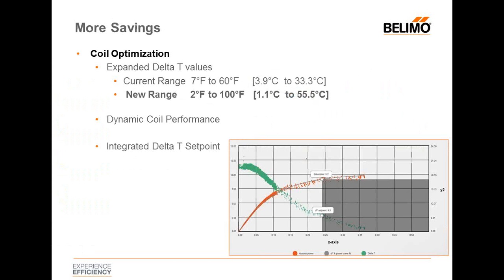Let's get into some of the core features for Energy Valve 3.0. At the core of the energy valve is coil optimization. We've expanded our delta T range, particularly on the higher end, going from 60°F all the way up to 100°F. We've had many requests from our Latin American market and for heat exchangers operating in the 70 or 80 degree delta T range. We've also had requests from colder environments needing higher delta T's for heating applications like condensing boilers, which typically have 90 to 100 degree delta T. This allows us to provide more savings on the heating side as well.